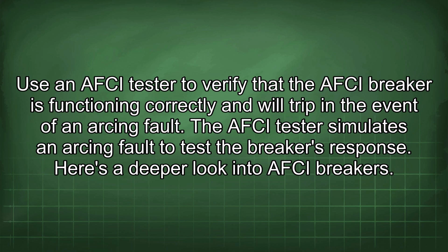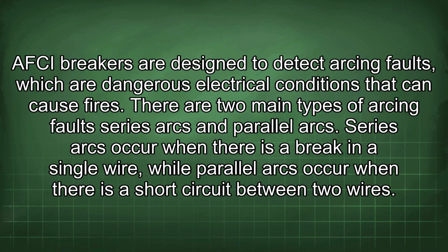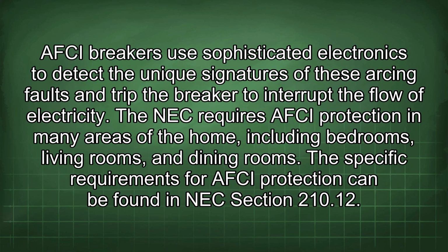Here's a deeper look into AFCI breakers. AFCI breakers are designed to detect arcing faults, which are dangerous electrical conditions that can cause fires. There are two main types of arcing faults: series arcs and parallel arcs. Series arcs occur when there is a break in a single wire, while parallel arcs occur when there is a short circuit between two wires. AFCI breakers use sophisticated electronics to detect the unique signatures of these arcing faults and trip the breaker to interrupt the flow of electricity. The NEC requires AFCI protection in many areas of the home, including bedrooms, living rooms, and dining rooms. The specific requirements for AFCI protection can be found in NEC Section 210.12.